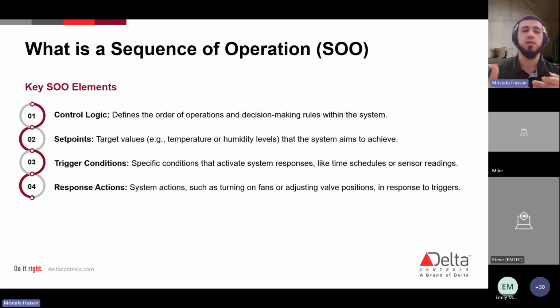But again, we can call them different things. This isn't out of a standards book, but the names are kind of self-explanatory here. So your control logic will define the order of operations and the decisions that the controller will take, right, to start returning that occupant comfort to a comfortable position. Maybe toggling off certain equipment when there's no occupancy. Again, reducing that energy usage. Right? Your set points are the target values, right? The specific values of temperature, humidity, maybe lighting levels, right? Again, completely related to occupant comfort. Or again, energy usage.